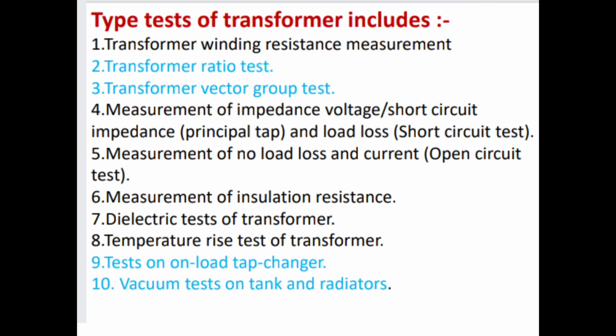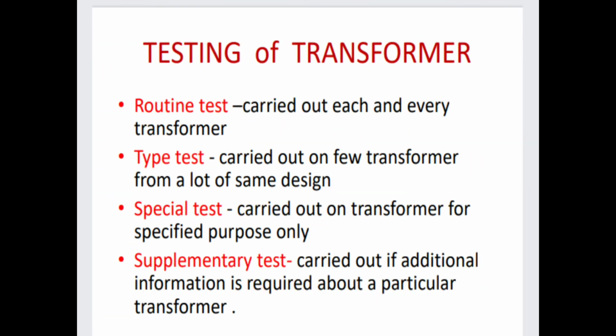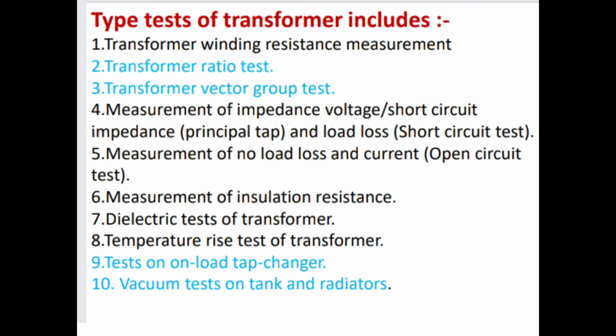Next is what the type test of transformer includes. We see when the type test is carried out. The type test is carried out on a few transformers from a lot of the same design. So some tests are included in the type test. First is transformer winding resistance measurement. Second is transformer ratio test. Third is measurement of vector group test.